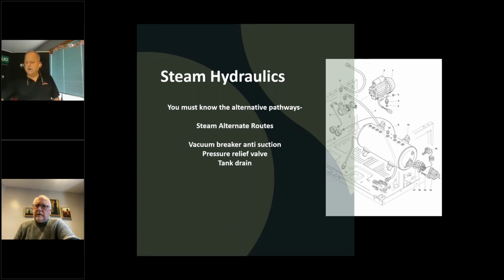So we've got a vacuum breaker, an anti-suction, and a tank drain. Tank drain, hey, half of them don't work because they're sitting in the bottom where we hide all the scale. But we have to have a pressure relief valve in case we turn this thing into a bomb. And remember that there are two pressure relief valves that you can buy. One is actually certified. It's been tested and it's been certified. There's a little gray portion on that valve at the top, and that is actually a seal. They used to make those seals out of lead. And it's just designed to exhaust the pressure.